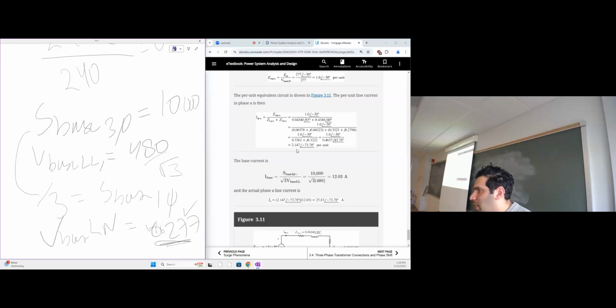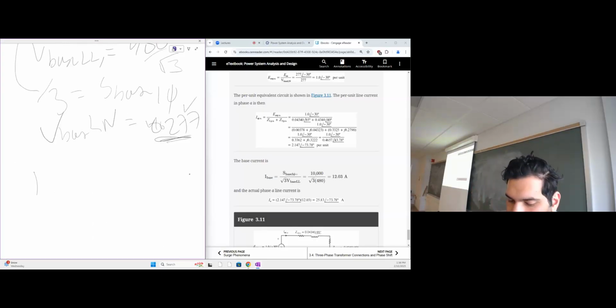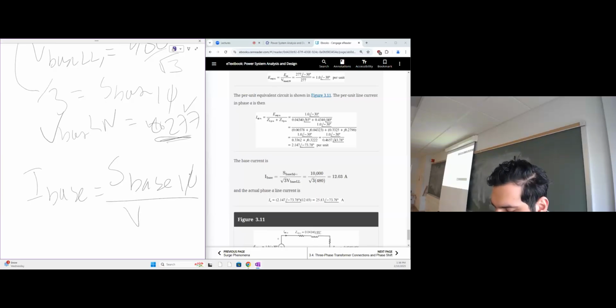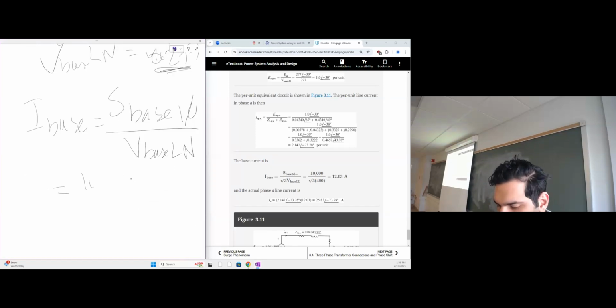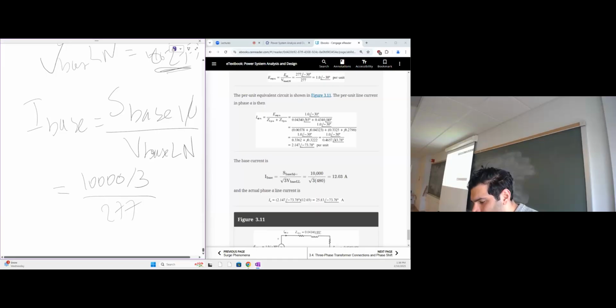But I'm asking about the real value of the current, so you need to get the base value of the current. So either you get S base 3 phase over radical 3 V line to line, or another equivalent form for I base is to use S base single phase over V base line to ground. So you would divide here by 10,000 over 3, and down there you would divide by line 277. I think those should give the same value. Okay? So you get 12.03. If I ask for the real actual value of the current, you need to multiply this value by 2.147 to get this value here. It will be 25.8 amperes with this angle.